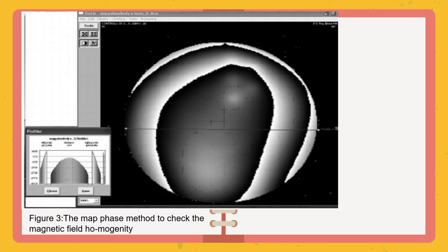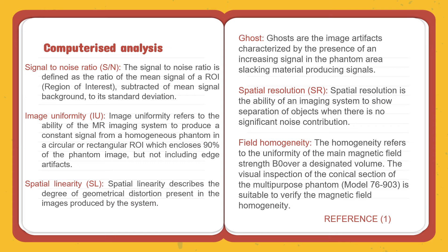We have computerized analysis using six parameters: signal-to-noise ratio, image uniformity, spatial linearity, ghost, spatial resolution, and field homogeneity. The signal-to-noise ratio is the ratio of the mean signal of an ROI subtracted by the mean signal of the background to the standard deviation. Image uniformity refers to the ability of the MRI system to produce a constant signal within a circular or rectangular ROI enclosing 90% of the phantom image.